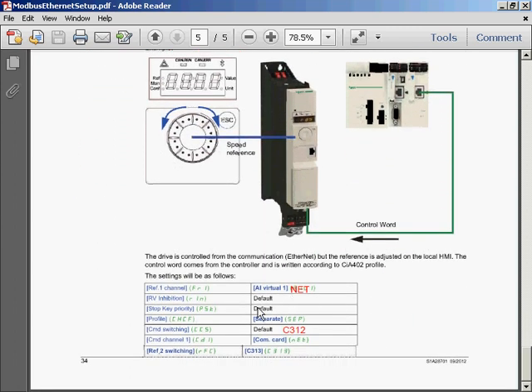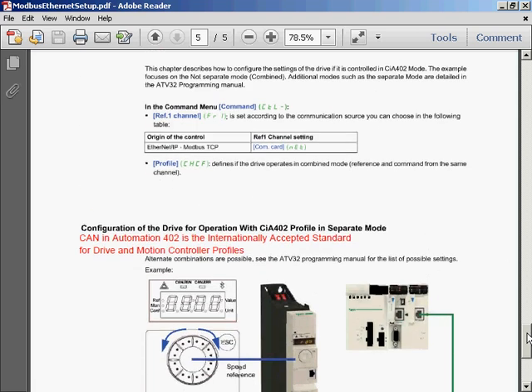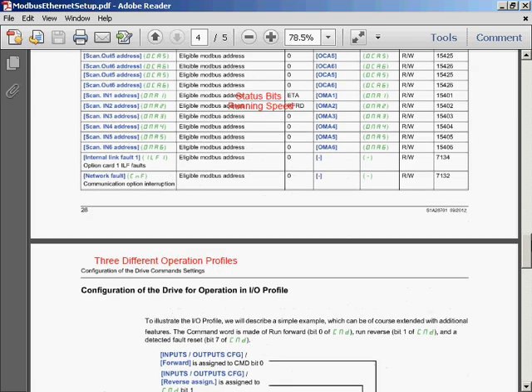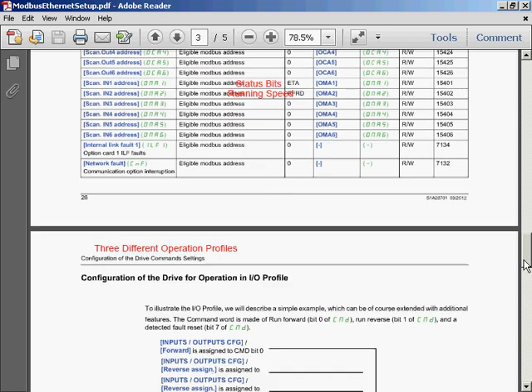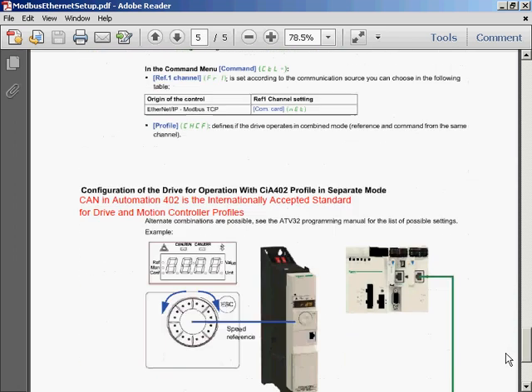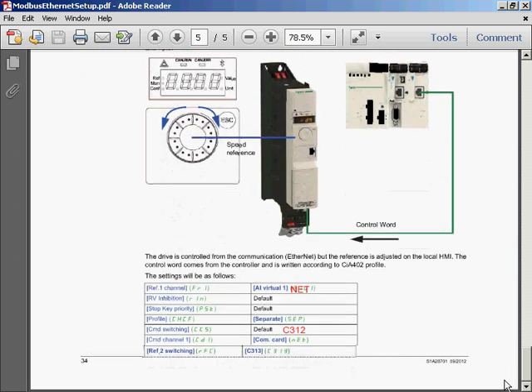So, this is what things look like. My first reference channel 1 is set to the comm network. My profile is set to separate. And the command switching is set to 312. This is the 12th bit of the control word that we talked about here. This control word. Scroll back down. And C313 is the 13th bit of that control word.